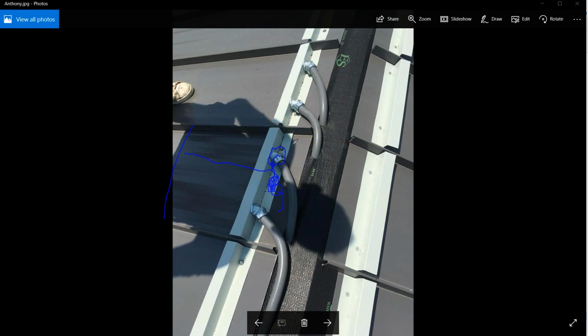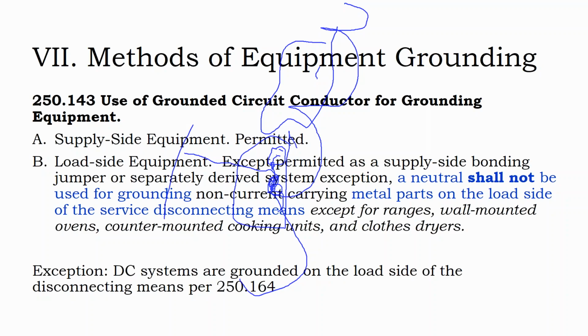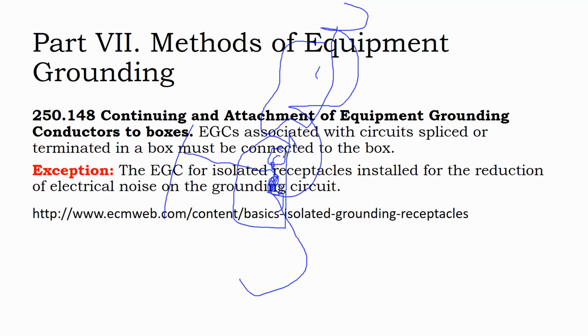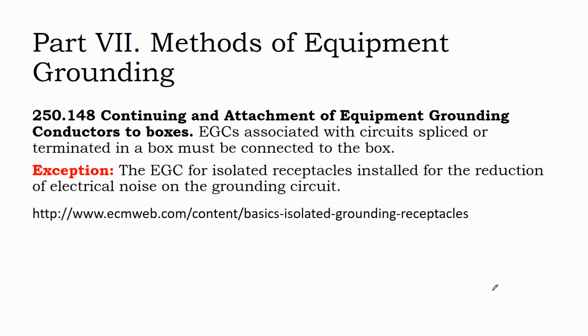And then I guess you get into this issue where you'd have to go through and ground each one. So you might actually find yourself taking some bare copper wire and just running it along the roof cap in order for this kind of specialty integrated internal conduit run to be code compliant. Of course, then we have the equipment ground conductors should be terminated inside of a box.